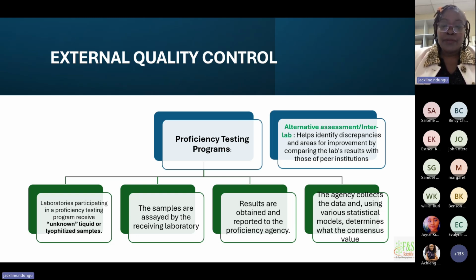At a bare minimum, you can also do split testing. I don't think you can completely fail to get a lab to compare yourself with, but if you completely cannot, then you can do split testing. By split testing, I mean you split your tests among the technologists and you see how their performance is, and you keep that as your EQA, external quality control proficiency testing. Plus many more. So yes, let's proceed.